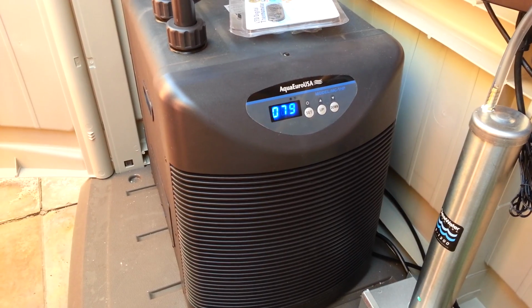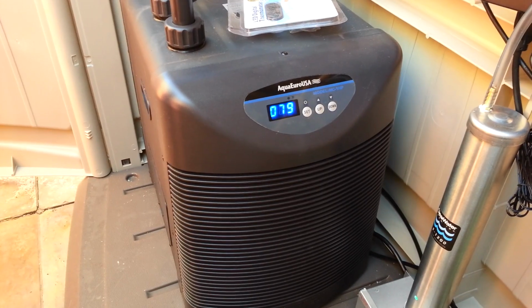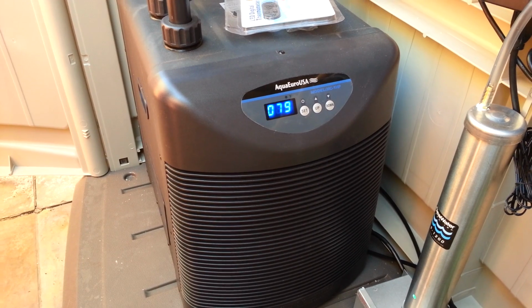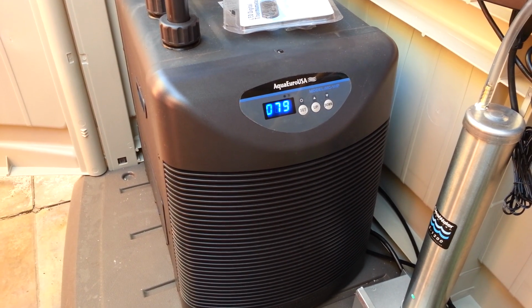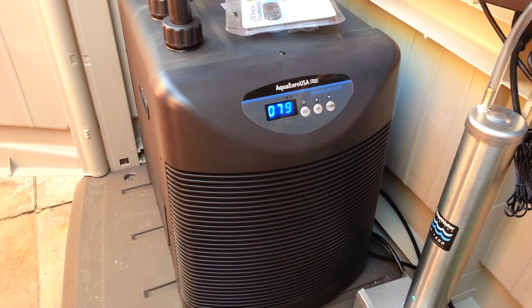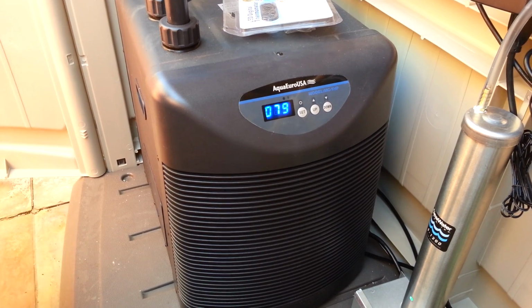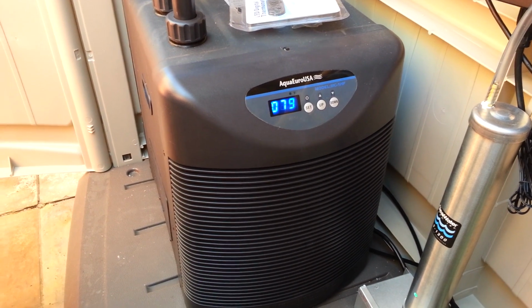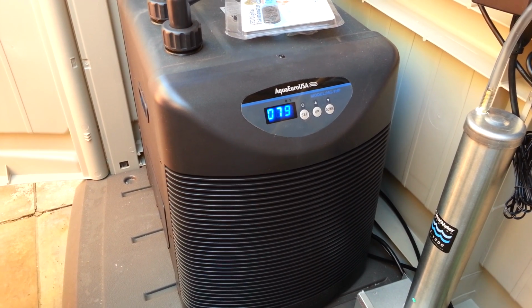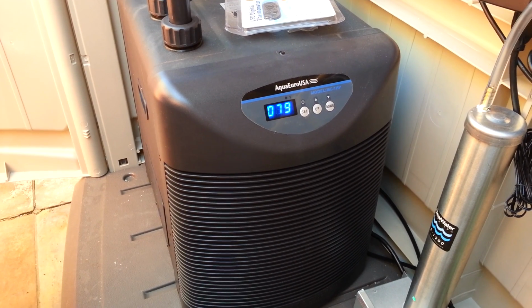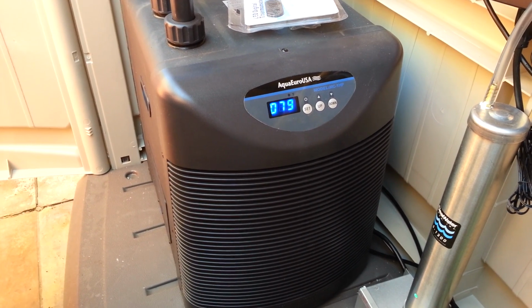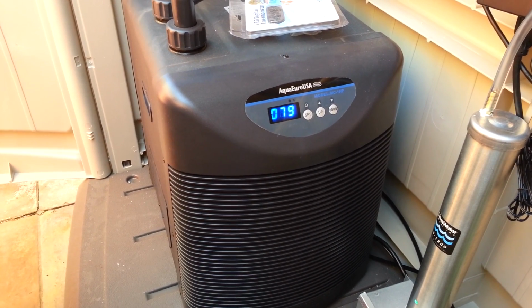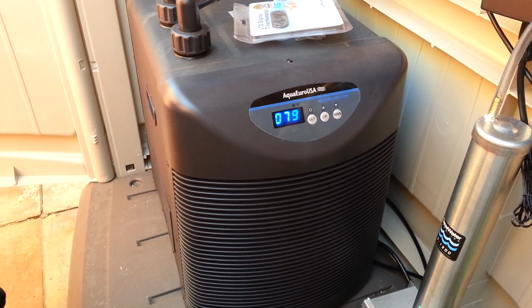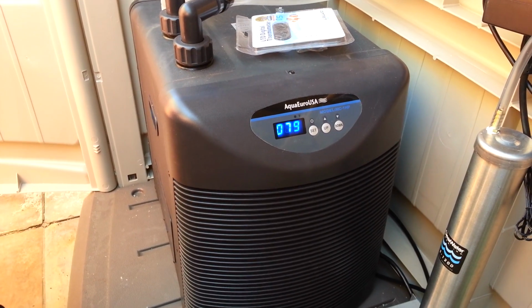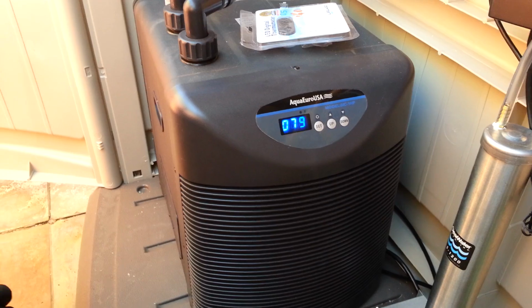When the chiller comes on, the temperature on the readout on the chiller actually goes up, which is, you know, obviously opposite of what it should be doing. Now the temperature on the other thermometer in the sump does go down a little bit, so it seems that the water is cooling, but the chiller isn't reading properly.